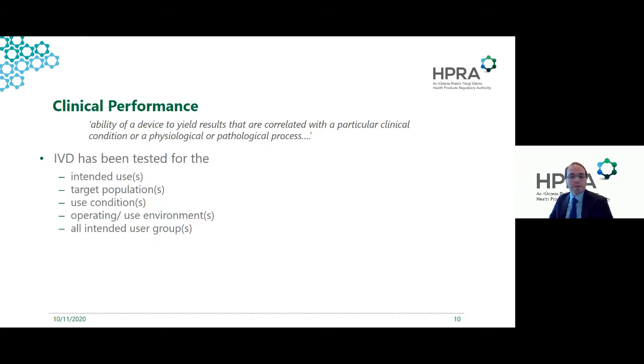So clinical performance, that's the link between the clinical condition in a patient and the device - how good is the device at actually predicting or detecting a specific physiological or pathological process? That's really in place to demonstrate that the IVD has been tested for the intended use in the right population, the target population, under the use conditions that it's going to be used on the market.